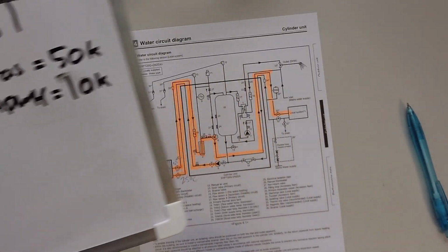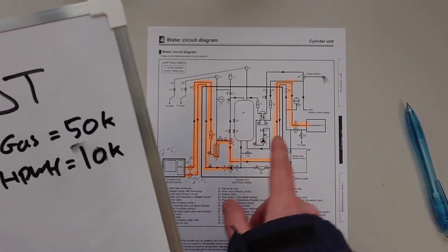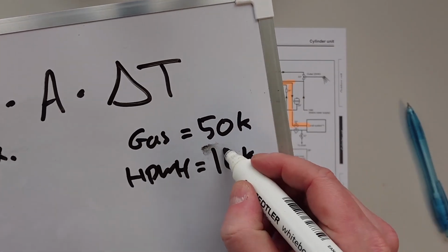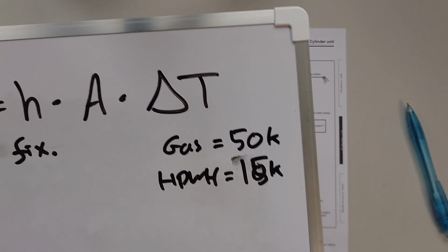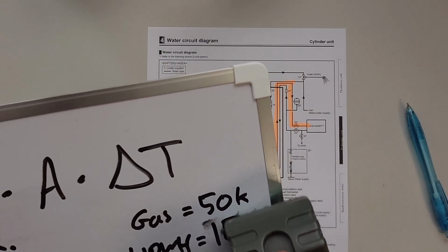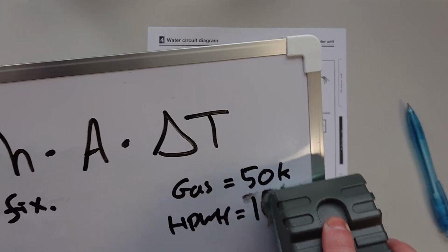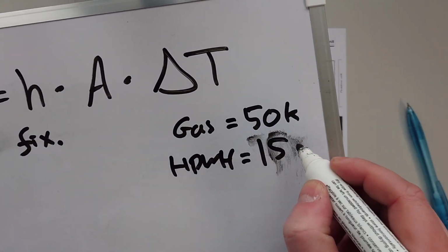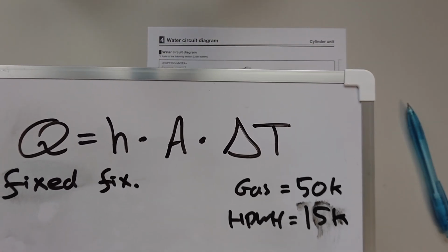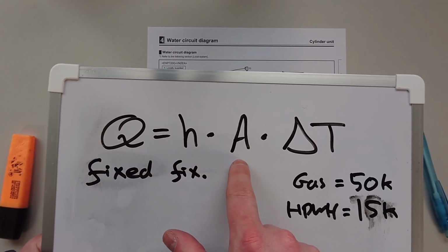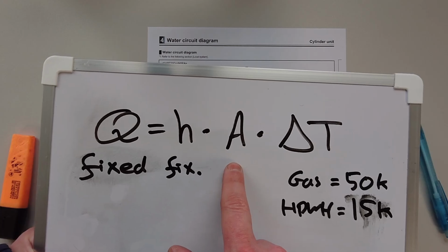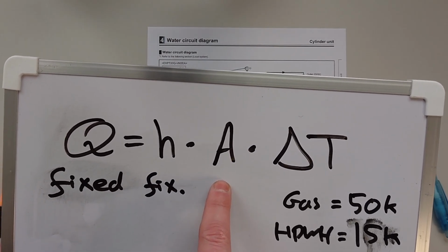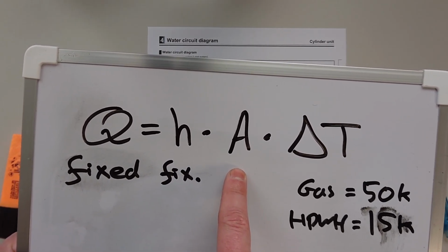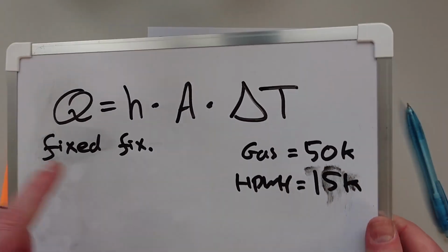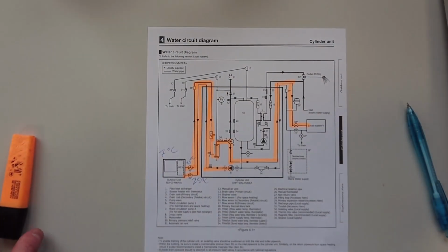That's not 10, is it? I was thinking it's 10 degrees across there, but it's actually 15. We are experts. But either way, it's a smaller number than the 50 that you have from your gas. So what that means is that the only way you can do this is to increase A. So the answer is yes, you probably will need a bigger heat exchanger for it, whether that be bigger radiators, underfloor heating, something else, but you need more, probably.